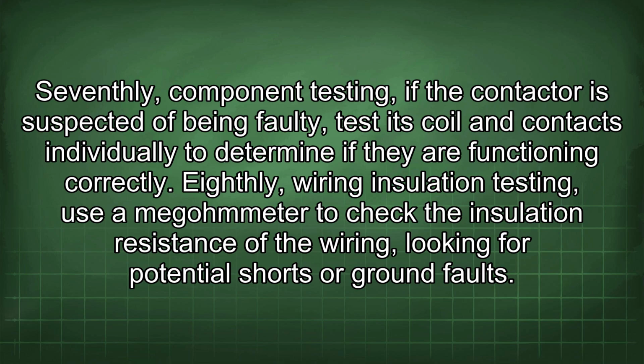Seventhly, component testing. If the contactor is suspected of being faulty, test its coil and contacts individually to determine if they are functioning correctly. Eighthly, wiring insulation testing. Use a megohmmeter to check the insulation resistance of the wiring, looking for potential shorts or ground faults.